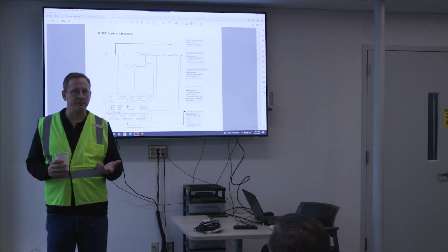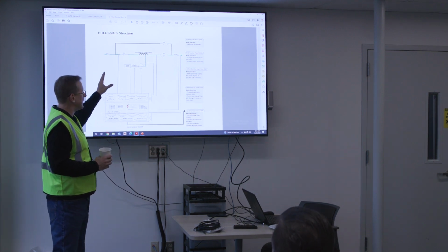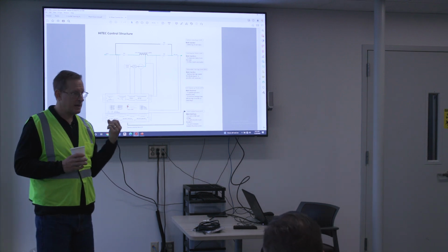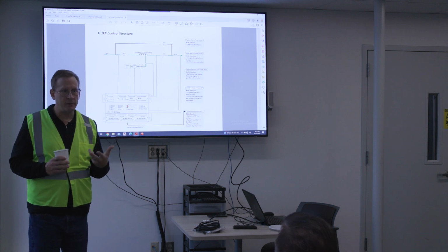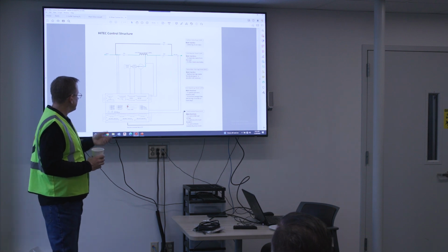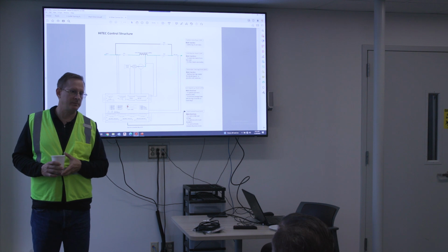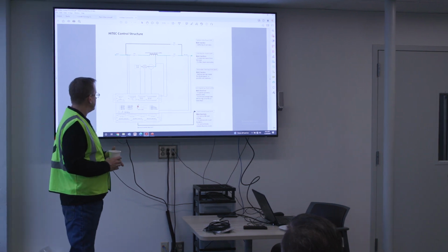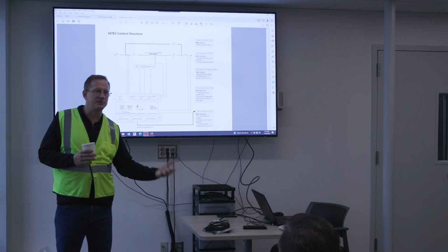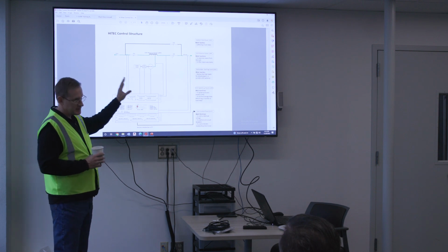It's also a monitoring device or a metering device because it's what is actively looking at your voltages, your currents. It's looking at your speeds for your diesel and your flywheel. All these measurements are taken by the Dicon. And then your Dicon is also, in some instances, a controller as well. So it's kind of the go-between between the PLC and the devices that are being controlled by the Hitec system. Okay, so the Dicon communicates with the PLC.